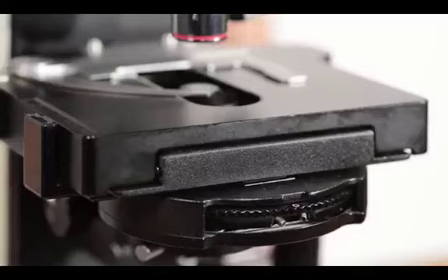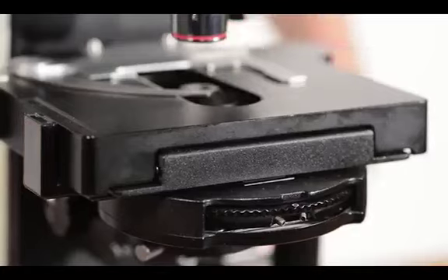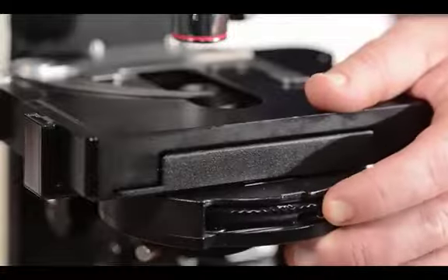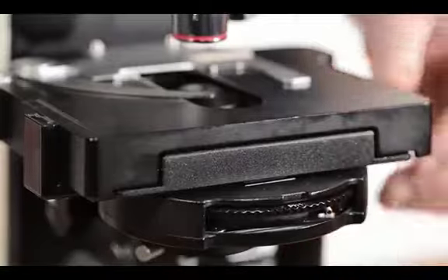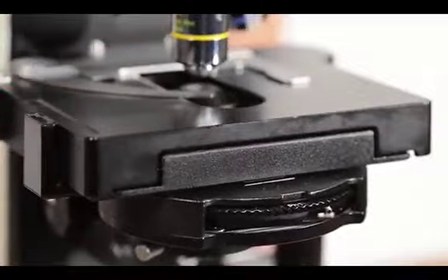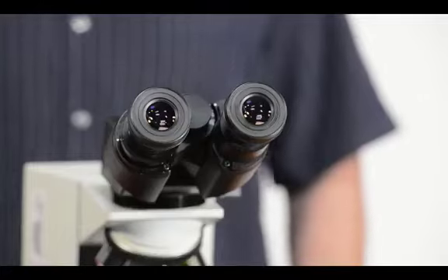Phase contrast microscopy allows us to view transparent specimens by increasing contrast and depth of field. In order to produce the best image possible, we need to align the phase contrast rings. To do this, we first change the filter on the condenser to pH1. Next, we change the objective lens to 10x.